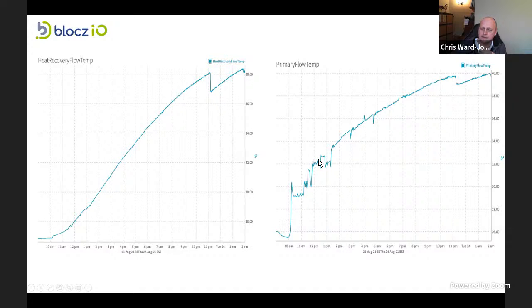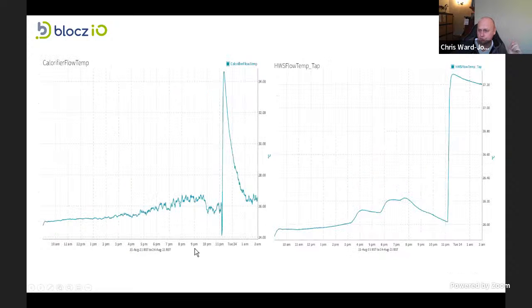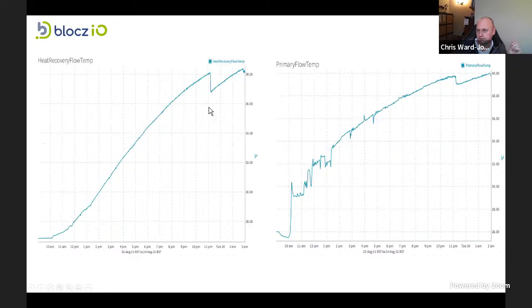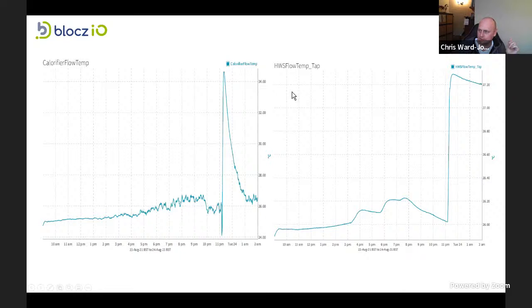This is what we're seeing inside the chassis effectively, the secondary loop, and as workloads and things change, you get a very real reaction. But the heating circuit itself acts like a thermal battery, so it smooths out those changes you see over here. That dip you saw around 11 o'clock in the evening - and yes, we were running tests that late at night - is us sucking a load of heat out of that heating circuit at the same time and putting it into the hot water.